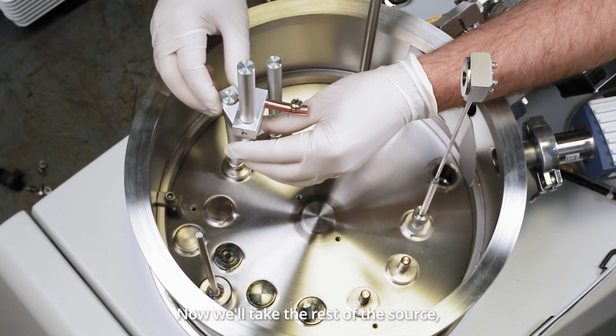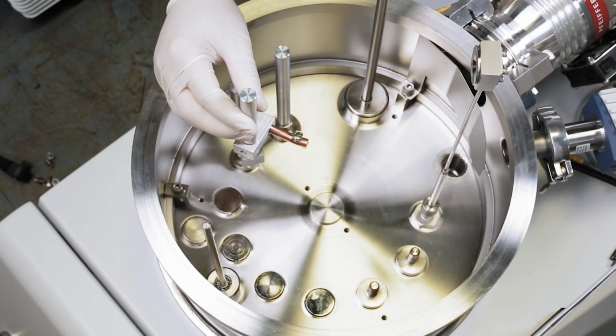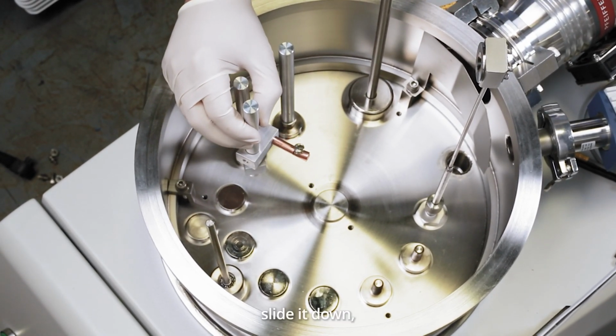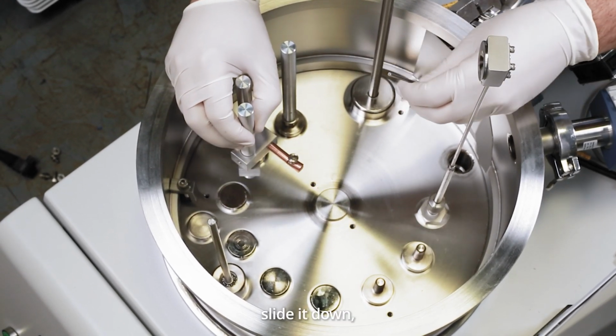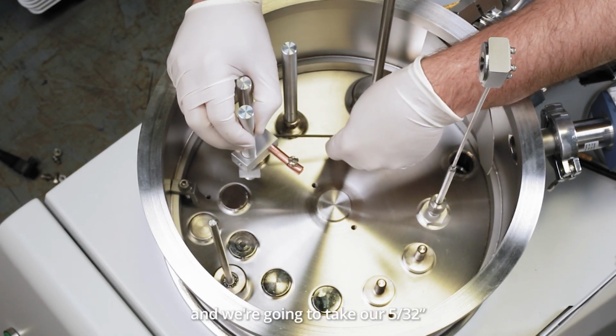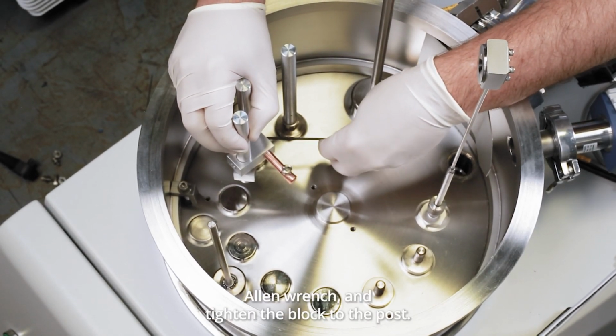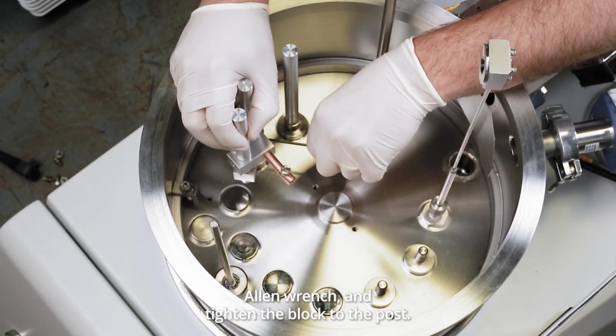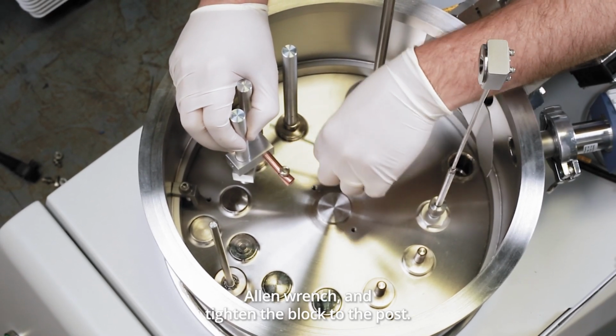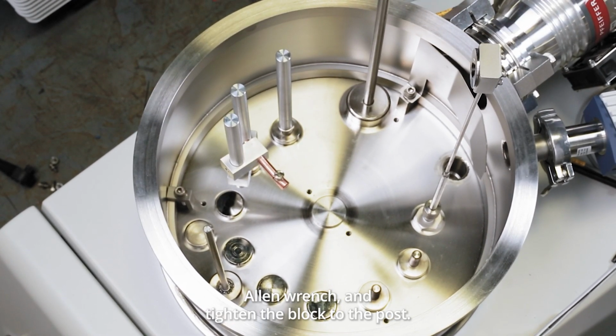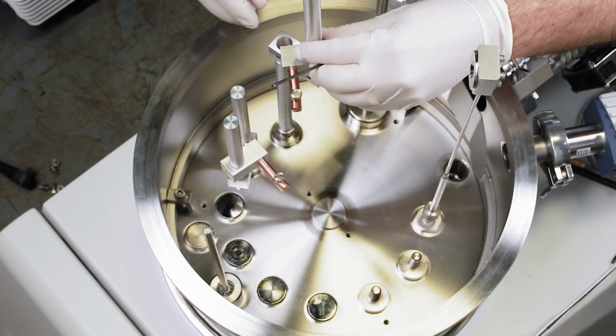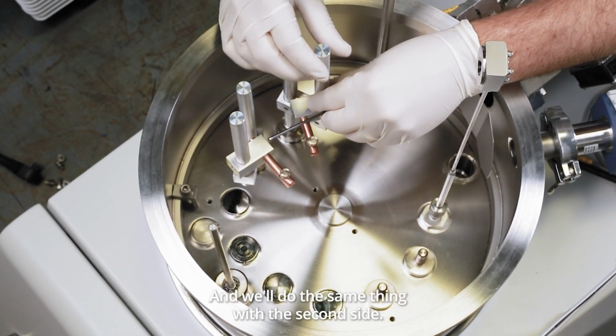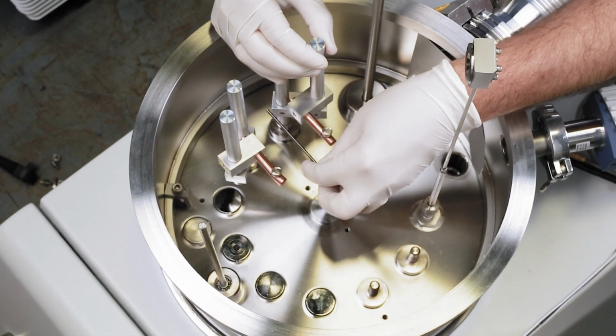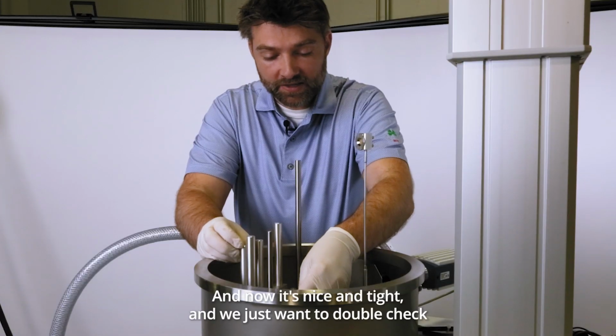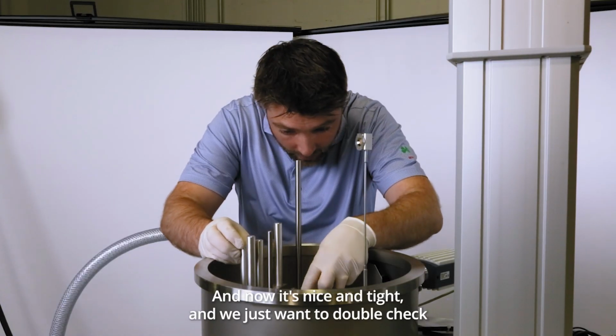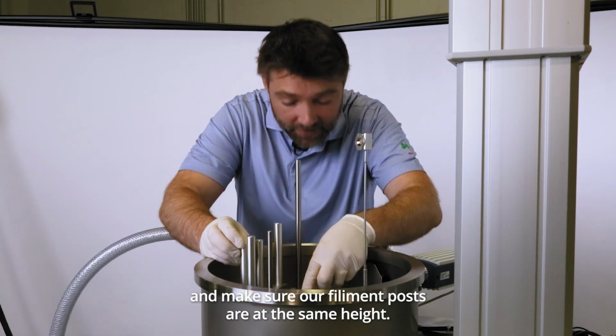Now we'll take the rest of the source, slide it down, and we're going to take our 5/32 Allen wrench and tighten the block to the post. And we'll do the same thing with the second side. All right, now it's nice and tight, and we just want to double check and make sure our filament posts are at the same height.